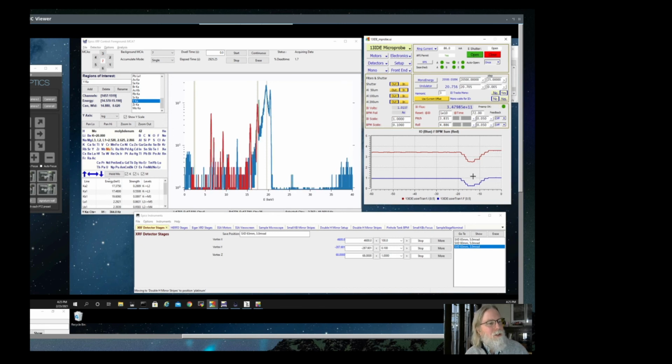But it's useful to be able to look at that and say that the blue curve is good and it's about 1 or 2, and that means that there's the right amount of beam. And the red curve is also on. The red curve is the intensity further upstream, and so is on even more often. In fact, we also have over here filters and shutters. So we have pieces of metal, aluminum foil, that we can drop in the beam. At 20 keV, they don't do much, but at 10 or even 7 keV, they can do a lot to attenuate the beam, which might be useful for controlling beam damage.